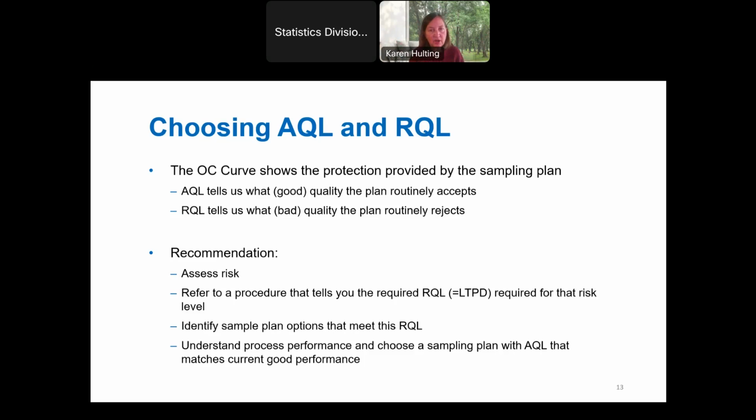Step one is always going to be risk assessment. We need to understand what risks we are taking on with this product. And so even if you're working in a manufacturing facility, you need to have a way to interact with your team members that can help you understand, in a medical device, what are the clinical implications of a defective unit getting out of the factory, right?